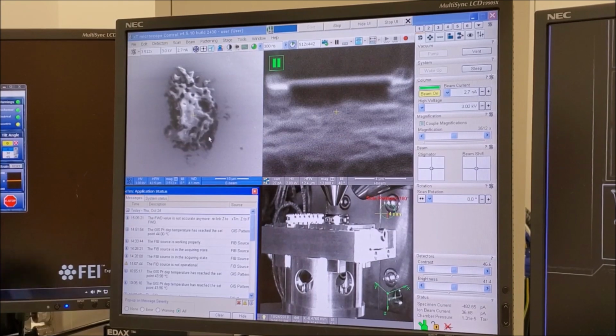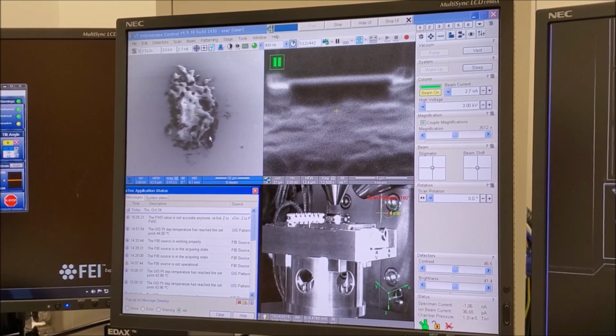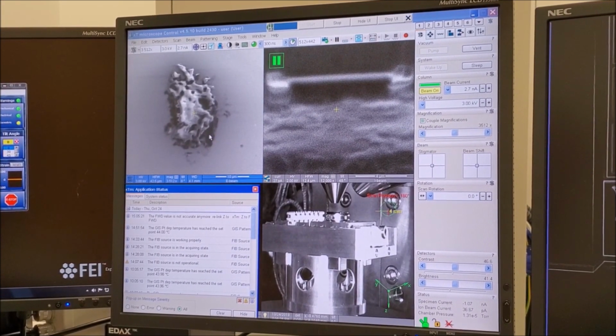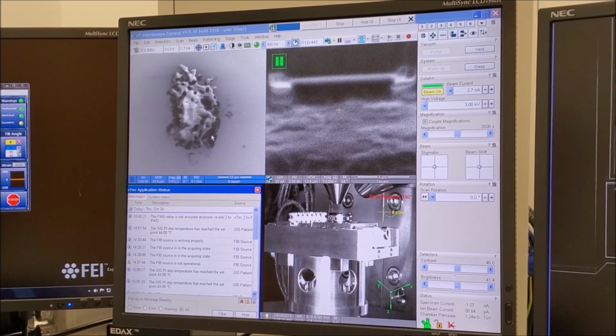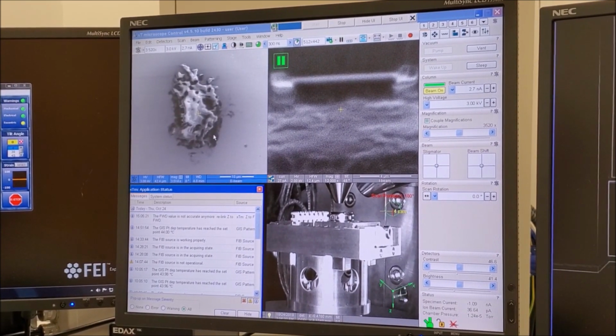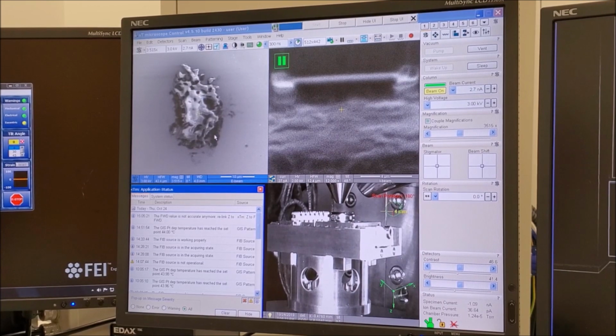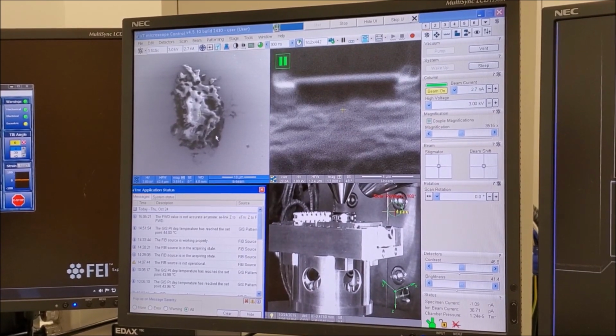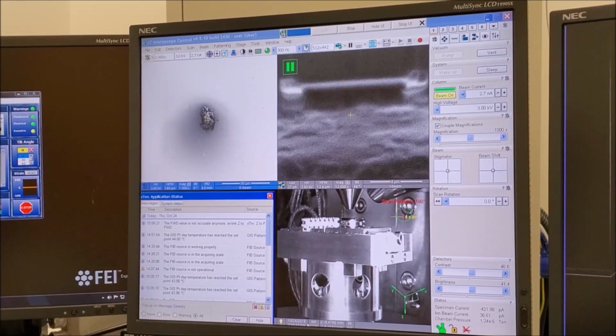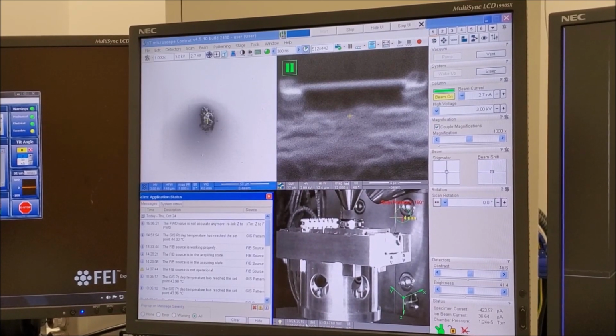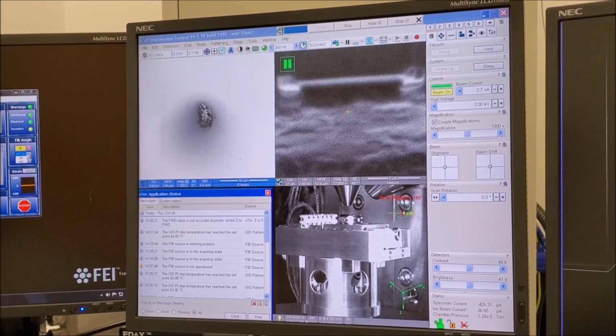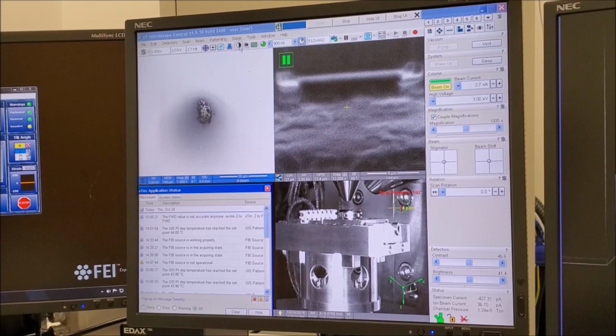Also keep in mind that alignment of the electron beam is sensitive to the voltage and the beam current selected. If either of these parameters are changed, then the alignment must be repeated to ensure the best image is obtained. Platinum deposition using the electron beam is most effectively accomplished using a low beam voltage and a high beam current.